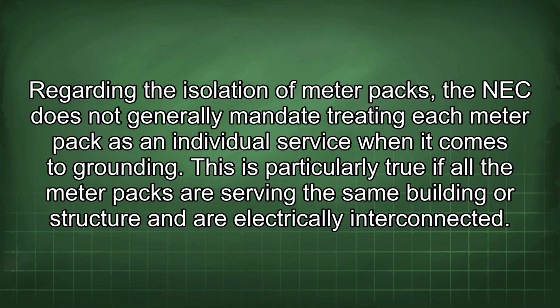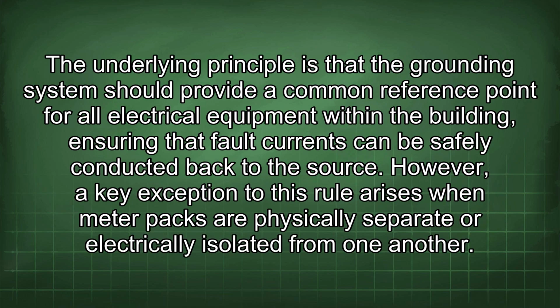Regarding the isolation of meter packs, the NEC does not generally mandate treating each meter pack as an individual service when it comes to grounding. This is particularly true if all the meter packs are serving the same building or structure and are electrically interconnected. The underlying principle is that the grounding system should provide a common reference point for all electrical equipment within the building, ensuring that fault currents can be safely conducted back to the source.